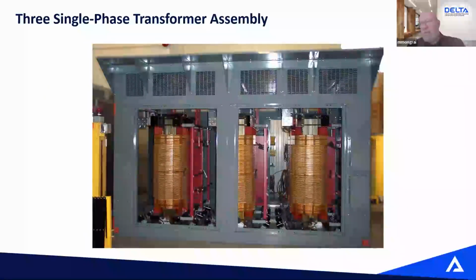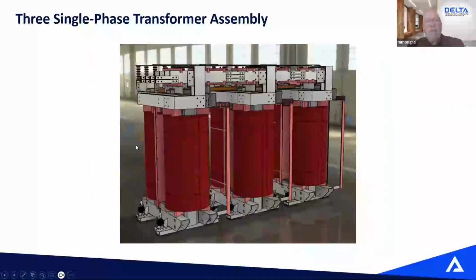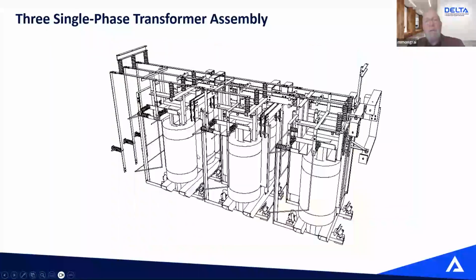In some cases, with a three-phase, three-legged core transformer, there's no way, there's no access. So in those cases, we can look at the option of a three single-phase transformer bank. So instead of doing a 1000 kVA three-legged core transformer, we will build three single-phase 333 kVA units, so a two-legged, two-winding transformer. Once reconnected together with busing and flex braid, they will recreate a 1000 kVA three-phase system. So those units are much smaller and more compact. And again, we can disassemble all the bus work from the transformer so that only the bare core and coil can go through the elevator and the hallway to be brought into the electrical room.